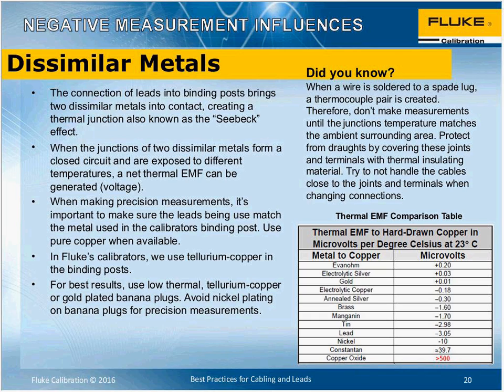So we have to be careful, usually to avoid nickel plating at all costs, and be going towards copper or gold plated or some of these other tellurium plated leads. So the problem there is we have to be very careful, but we're all about the temperatures as well as the dissimilar metals. So if we can keep everything at the same temperature, that reduces the effect. So we need to be careful that we shield our terminal connections from drafts.